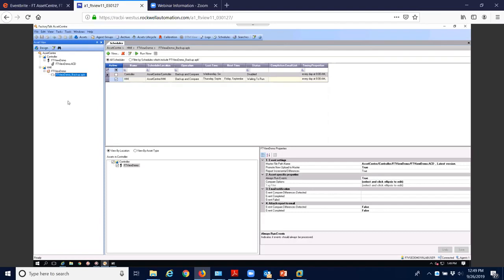You can do updates while everything's online and make modifications. The issue you run into is not from a ThinManager environment or anything else, because at that level you're just providing it content. If you make modifications to the library set, or if you're doing upgrades, in most cases it doesn't cause issues. The problem is usually when you're making modifications and changes. Because of the AOIs, as everybody here knows and has glared and yelled at me about, we can't make modifications with AOIs online. You can overwrite or replace an AOI, you just can't make changes to them, and you can't make modifications inside of the code.